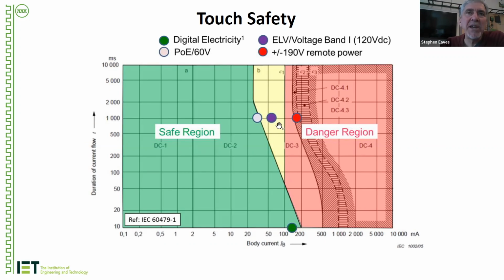So ELV, going back to ELV, is kind of in a yellow region. It hasn't entered into DC3, but it wouldn't be considered, I would say, safe. It's still in a questionable region. If you have, say, a weak heart or low skin resistance, it's still not a great spot to be. You can see here's plus or minus 190. This is a common communication powering system, remote communications. This has a fairly high exposure for line-to-line exposure. And then here's another very familiar one, this sort of whitish dot, power over Ethernet, or 60 volts DC. It might also be in a similar region as 48 volt power and telecommunication systems.